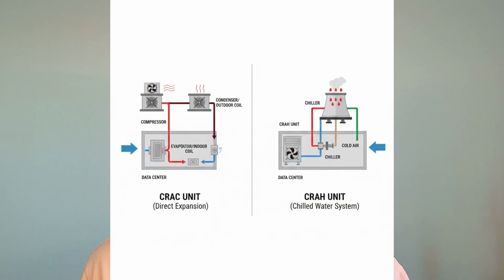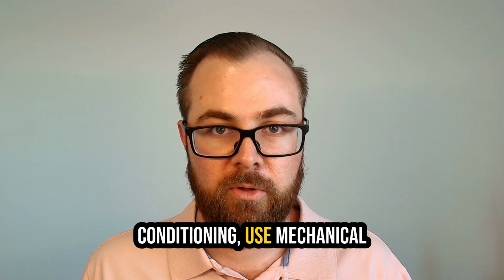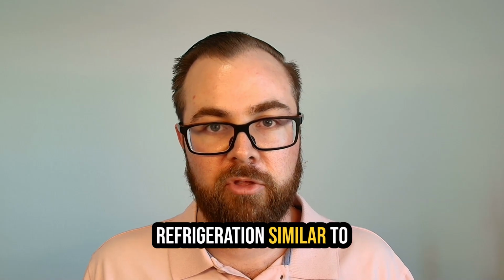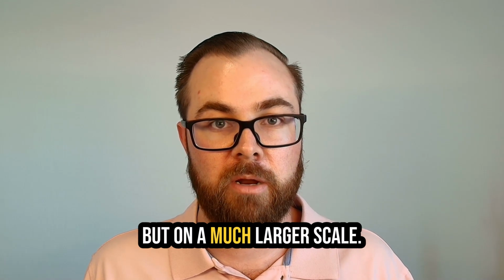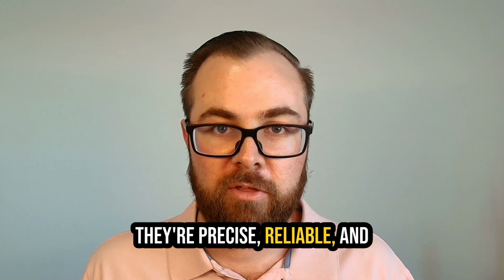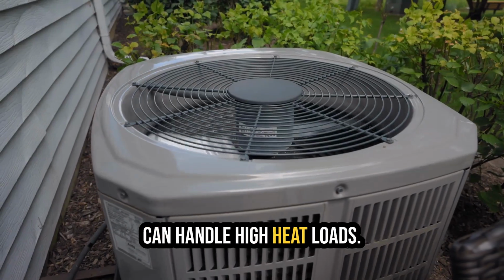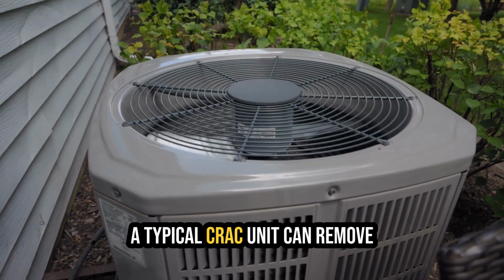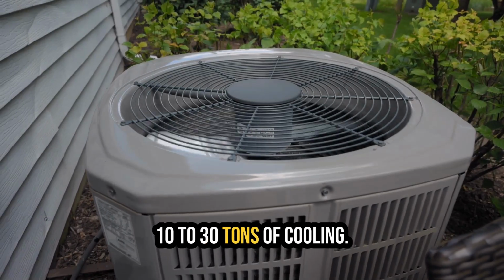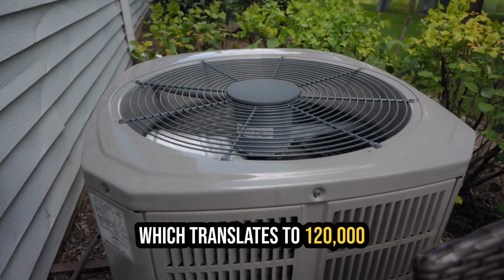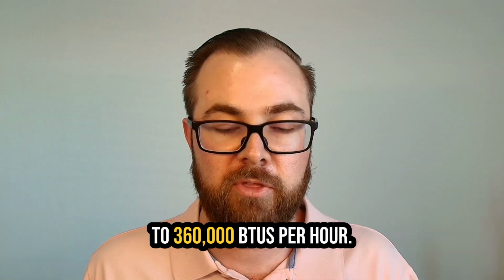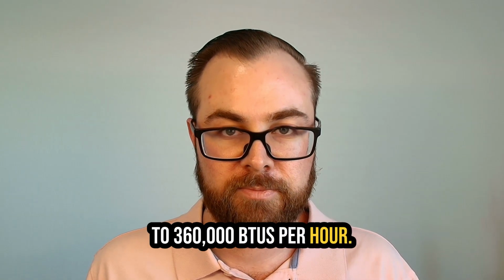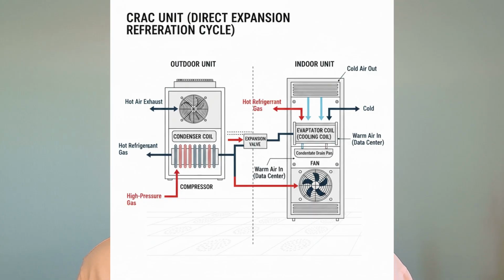CRAC and CRAH units are the workhorses of data center cooling. CRAC units, computer room air conditioning, use mechanical refrigeration, similar to your home air conditioner, but on a much larger scale. They're precise, reliable, and can handle high heat loads. A typical CRAC unit can remove 10 to 30 tons of cooling, which translates to 120,000 to 360,000 BTUs per hour. These units use direct expansion refrigeration cycles.